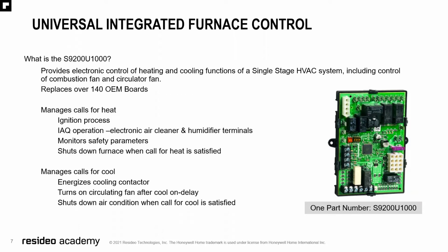It will also manage calls for cool, energizes the cooling contactor. You can set up a circulating fan cool on delay, and it will go ahead and shut down the air conditioning when a call for cool is satisfied. And it's just one part number for over 200 crosses, S9200U 1000.